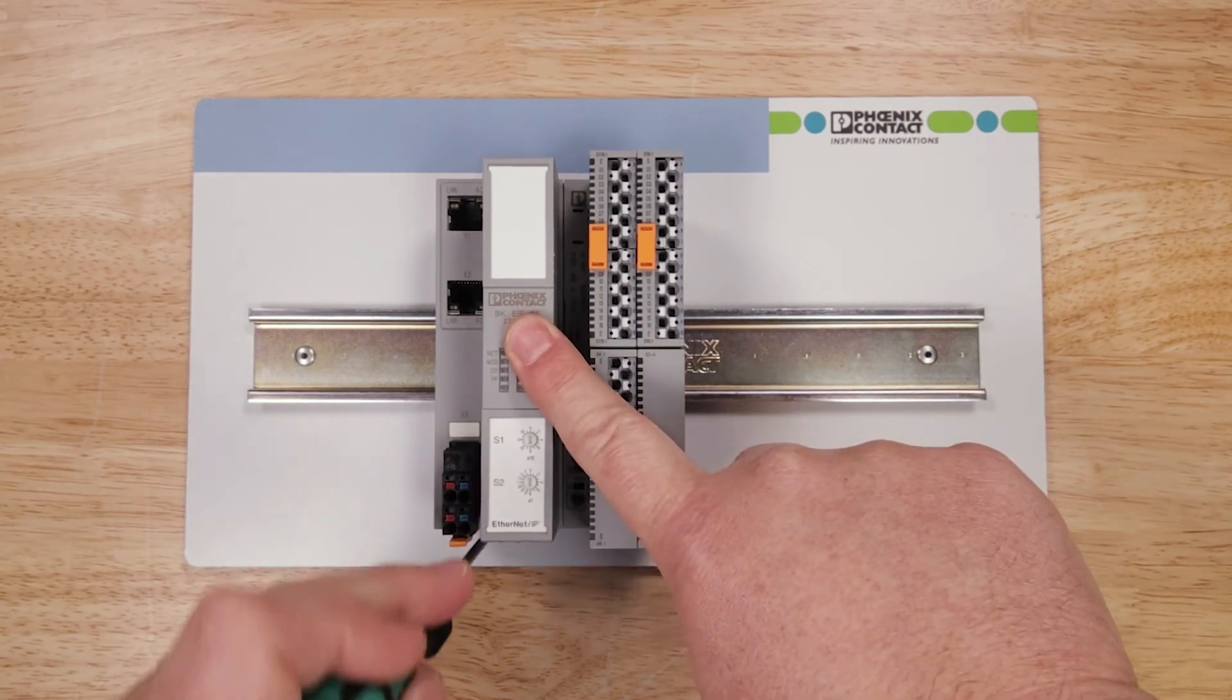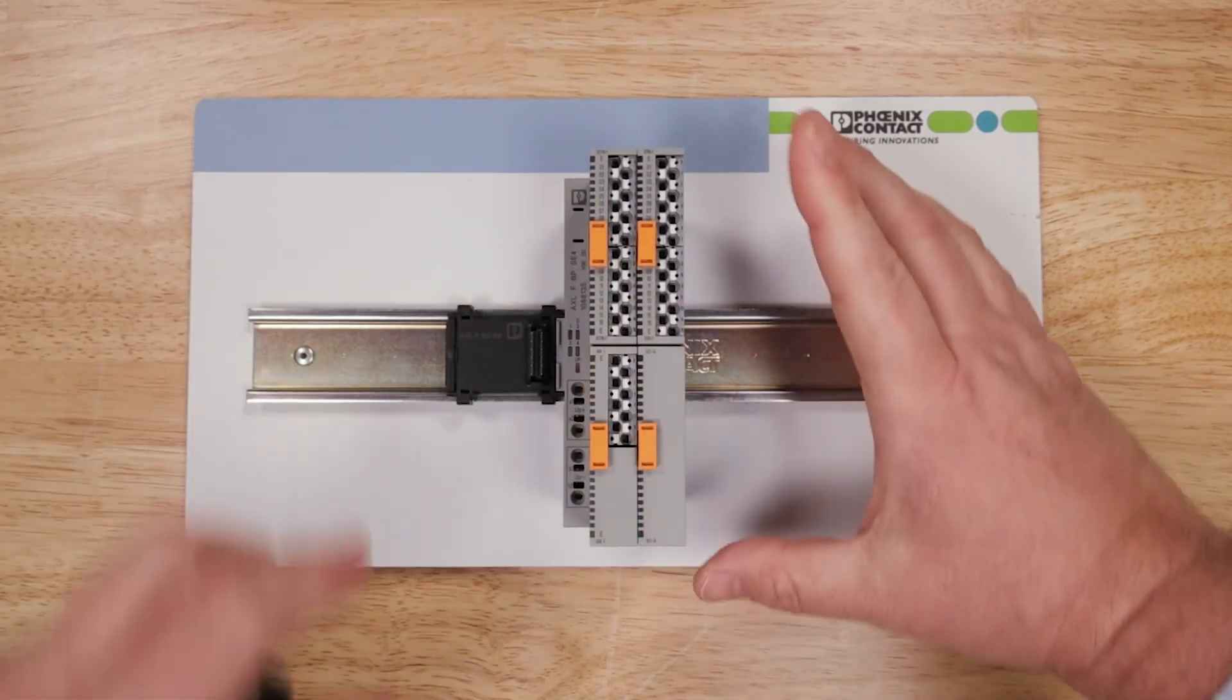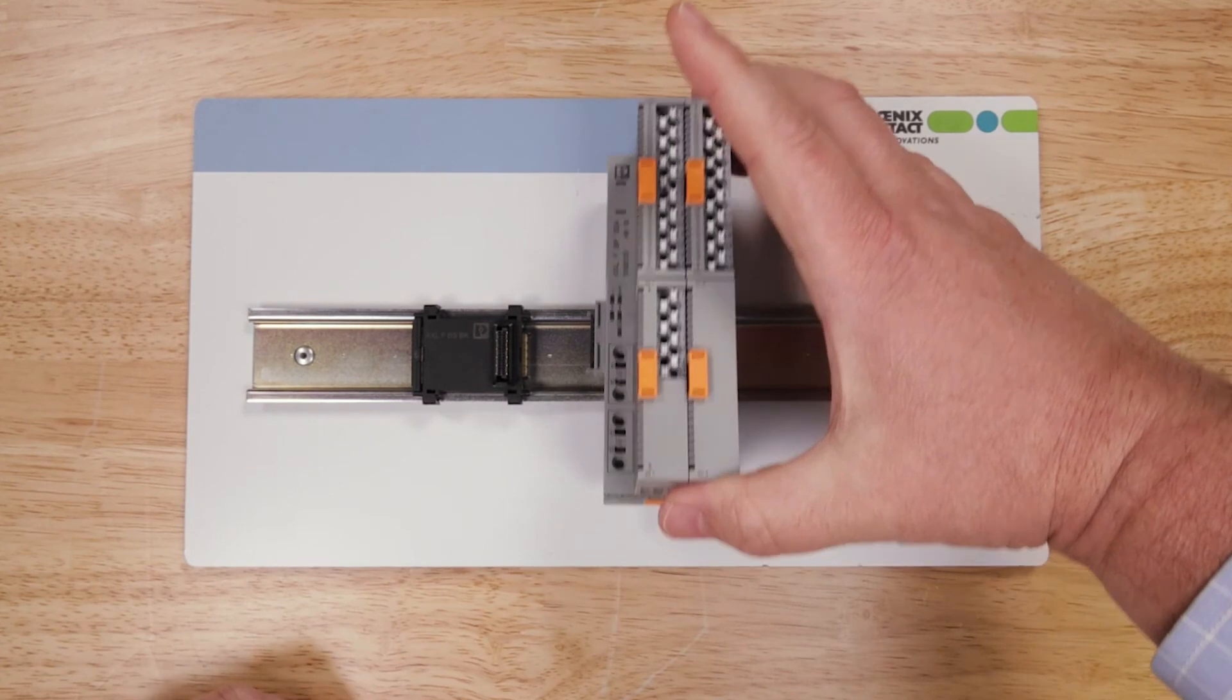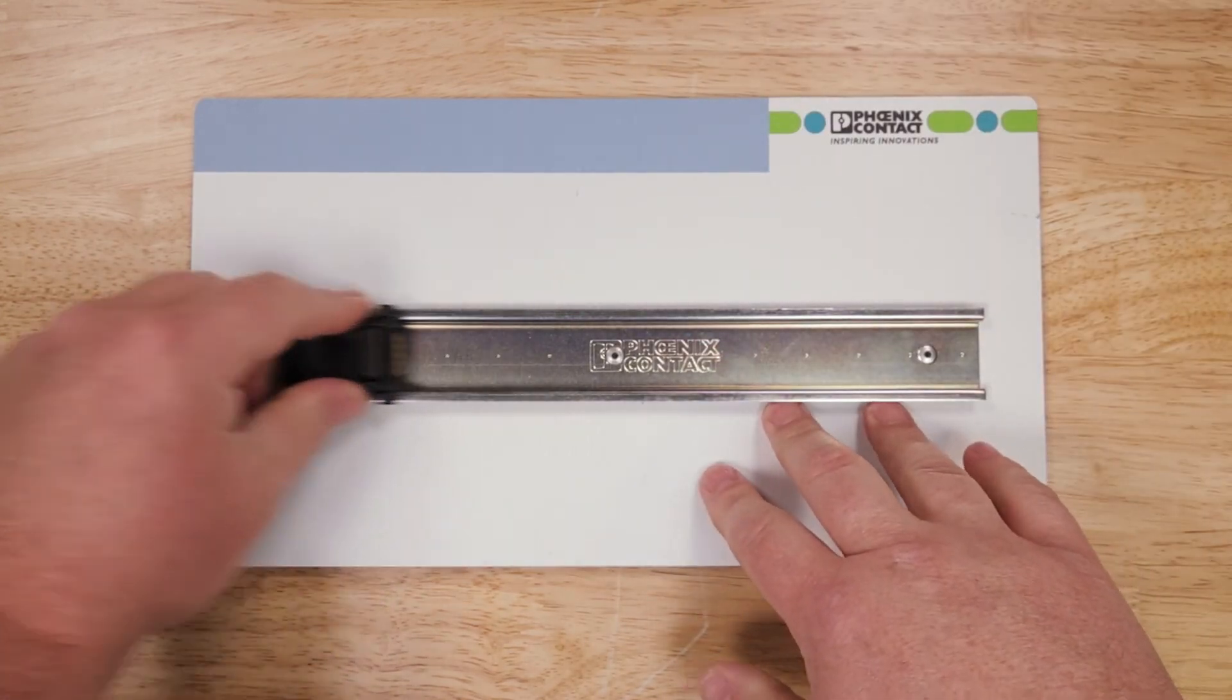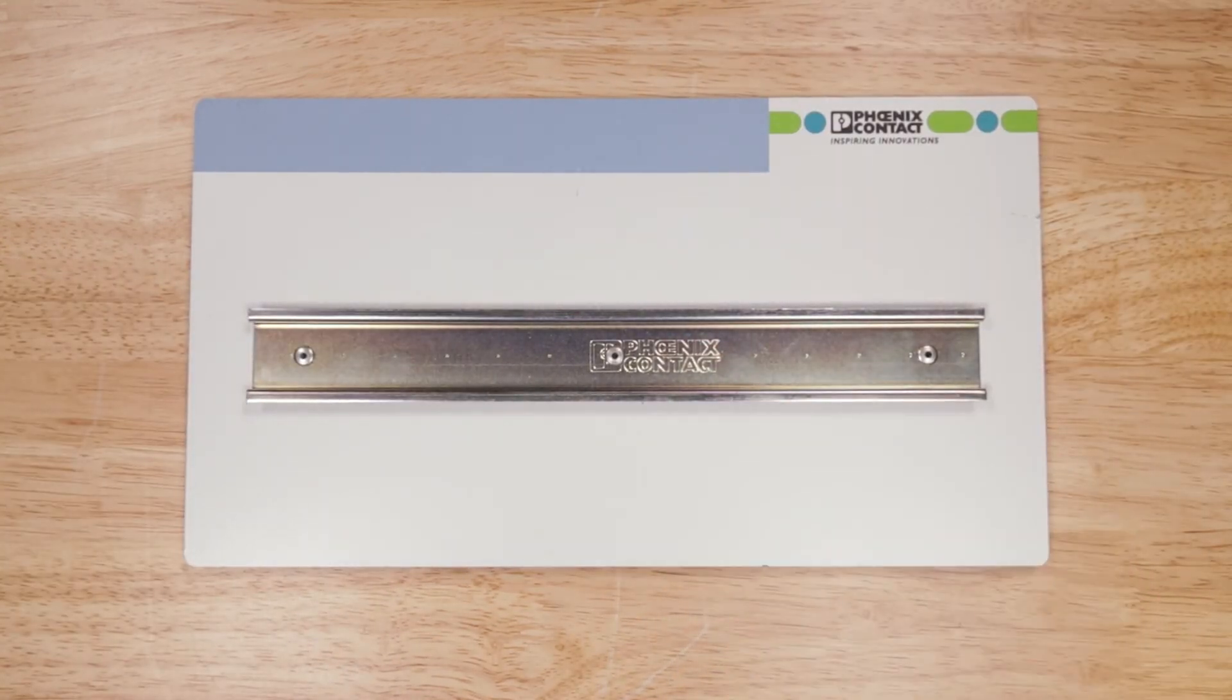Now if I want to remove the Smart Elements base, I'll have to remove the bus coupler first, because the bus coupler overlaps the backplane connection. Remove the bus coupler, slide the base or the backlink piece off, and then simply remove the Smart Element base and the backlink base.